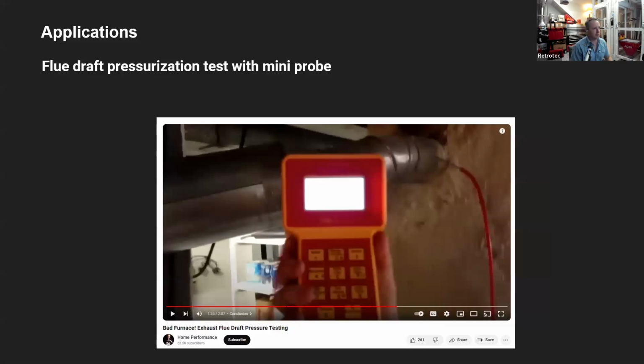Similar with flue draft pressurization tests. Again, you need a rigid metal probe to access that flue pipe. Here you can see Corbett was using our old DM2, which works great, but really that manometer is kind of overkill for this application, even though it works just fine. You set it to pascals, you can see if it's drafting or not. But now, with the Solo, you just need a less complex device to do the same thing.